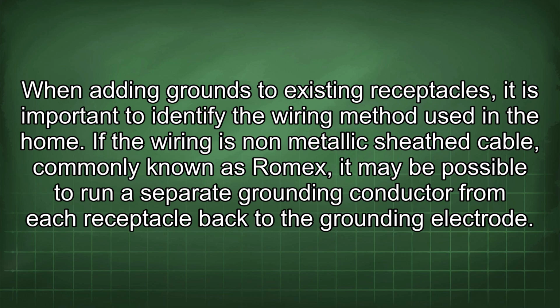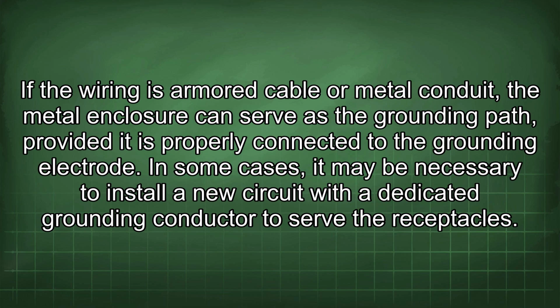When adding grounds to existing receptacles, it is important to identify the wiring method used in the home. If the wiring is non-metallic sheathed cable, commonly known as Romex, it may be possible to run a separate grounding conductor from each receptacle back to the grounding electrode. If the wiring is armored cable or metal conduit, the metal enclosure can serve as the grounding path, provided it is properly connected to the grounding electrode.